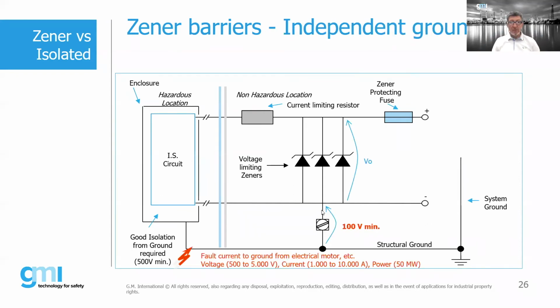Yeah, it's actually very good practice because you cannot test it otherwise. I mean, you can test it, but you need to shut down or commit the air. You need to make sure there is no presence of gas in some area, in zone 0. How do you do that?